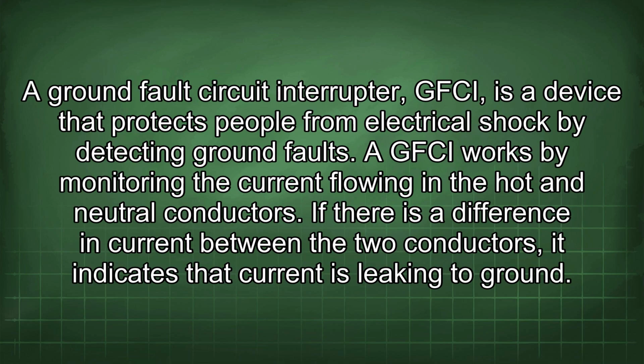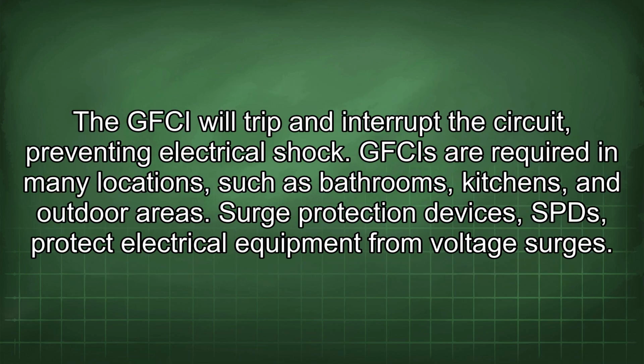A ground fault circuit interrupter, GFCI, is a device that protects people from electrical shock by detecting ground faults. A GFCI works by monitoring the current flowing in the hot and neutral conductors. If there is a difference in current between the two conductors, it indicates that current is leaking to ground. The GFCI will trip and interrupt the circuit, preventing electrical shock. GFCIs are required in many locations, such as bathrooms, kitchens, and outdoor areas.